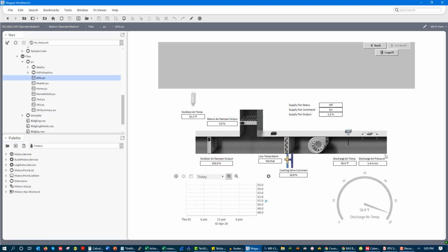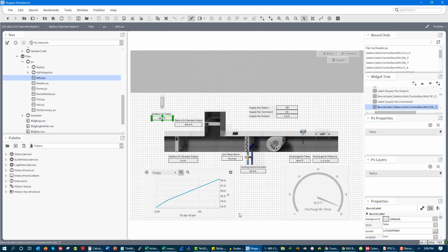Then we have our just standard graphics. These are graphics that are hard bound to the actual points themselves. If we go and look at a point and I click on it, we'll see that it's actually bound to that specific controller. We can see that right there. It's not relativized, it's not aliased. And because of that, it will definitely make it easier to make graphical changes, especially if you want to make a graphical change for one device.